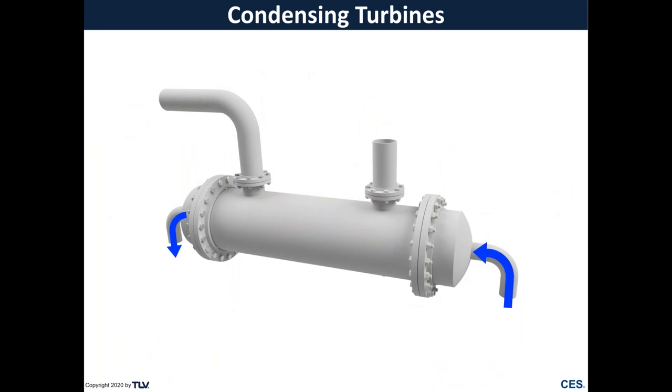This shows the flow path through the intercondenser. Cooling water is circulated through the tubes, while the steam and air mixture from the first stage ejector enters the shell, the steam is condensed, and the air is removed by the second stage ejector to the after condenser.